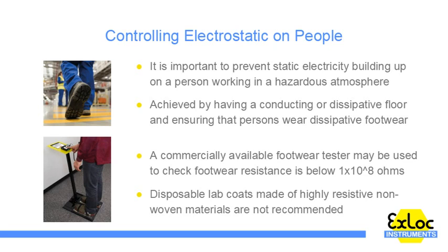Dissipative footwear has an upper and lower resistance requirement. The upper level, specified as 1 times 10 to the power of 8 ohms, is low enough to prevent the build-up of electrostatic charge in most situations, and the lower level offers some protection in the event of accidental contact with mains electricity.